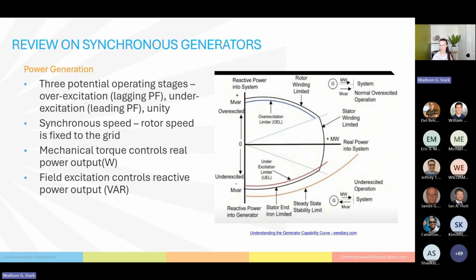At this point, the generator voltage is going to be higher than the system voltage. So because it's higher, it's able to push those VARs and the wattage into the system. At unity, power factor of 1, the generator is pushing only real power. It is not pushing or consuming reactive power at all. It is only pushing real power into the grid. This is kind of an ideal scenario used in math and theory, but a situation where a generator is pushing exclusively real power really doesn't happen.